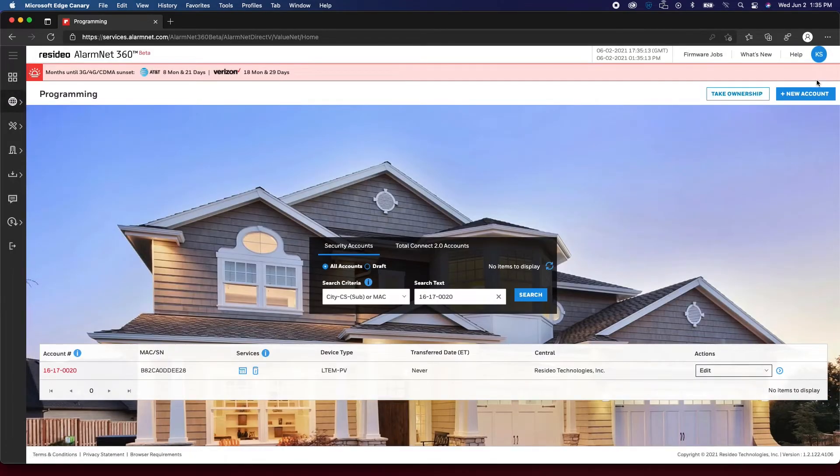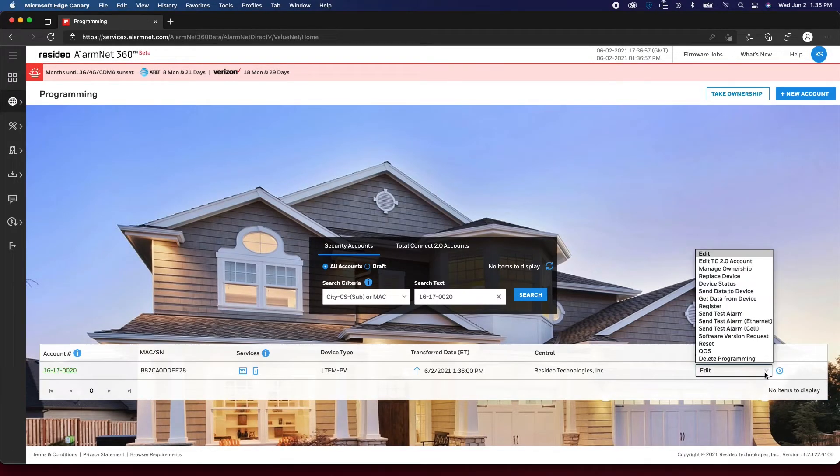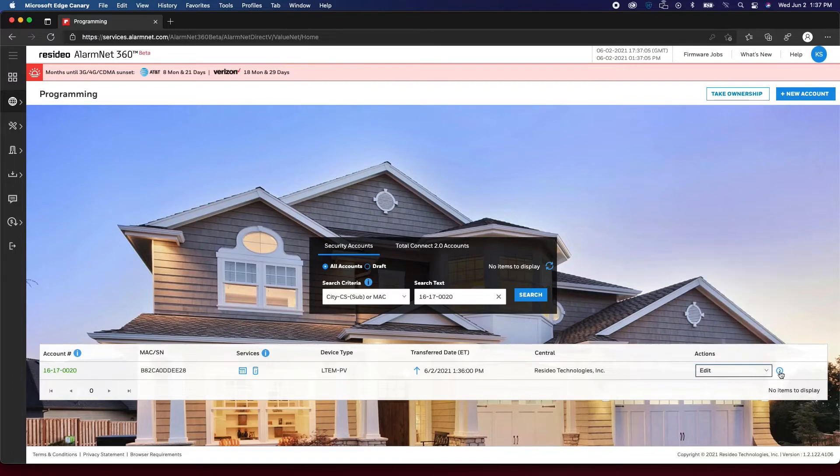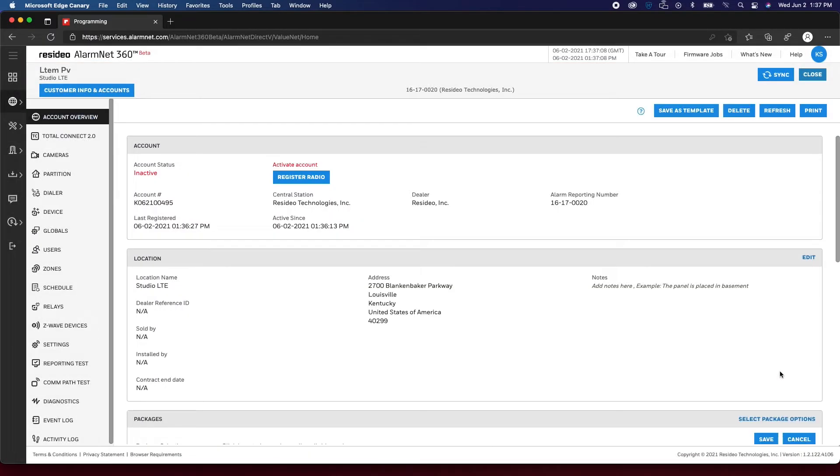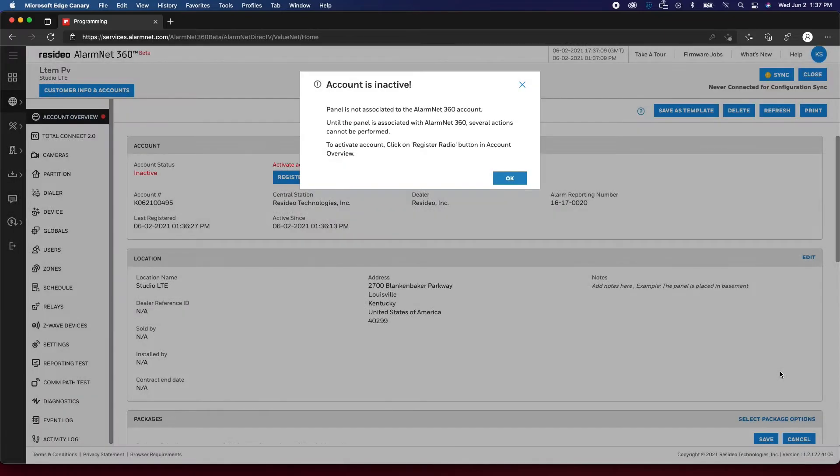After completing the communicator setup and with the account pulled up on the programming page in AlarmNet360, choose Edit from the Actions drop-down menu on the right-hand side, then click the blue arrow. You will be prompted that the account is inactive. Click OK.